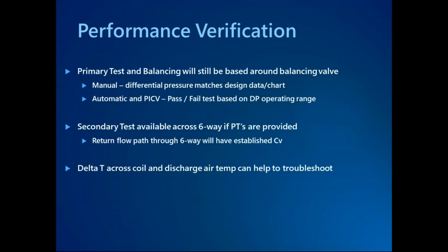And then last thing, just to reiterate and touch on a little more detail, when it comes to balancing and commissioning and testing and verifying performance of a 6-way kit, it really is nothing different than what you guys have been doing with manual balancing valves, automatic balancing valves, pressure independent control valves, even energy valves that you've seen to date in traditional 2-way and 3-way kits. We're just making the control valve a little bit more complex.